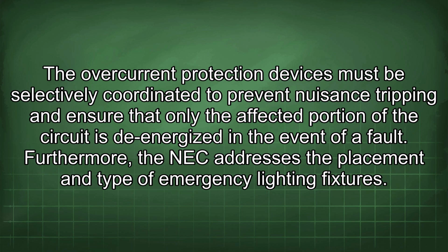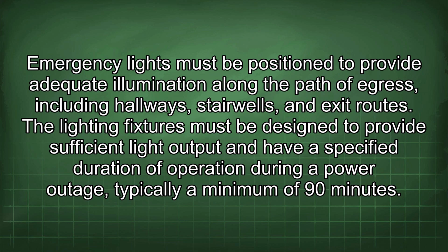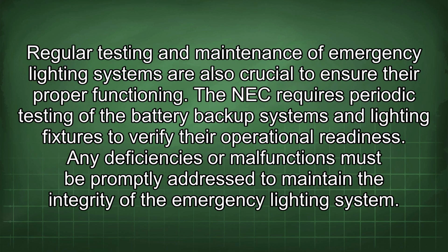Furthermore, the NEC addresses the placement and type of emergency lighting fixtures. Emergency lights must be positioned to provide adequate illumination along the path of egress, including hallways, stairwells, and exit routes. The lighting fixtures must be designed to provide sufficient light output and have a specified duration of operation during a power outage, typically a minimum of 90 minutes. Regular testing and maintenance of emergency lighting systems are also crucial to ensure their proper functioning. The NEC requires periodic testing of the battery backup systems and lighting fixtures to verify their operational readiness. Any deficiencies or malfunctions must be promptly addressed to maintain the integrity of the emergency lighting system.